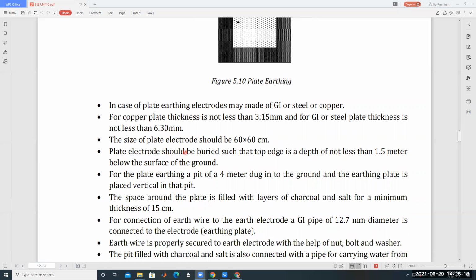The size of the plate electrode should be 60 by 60. Generally we have to maintain this, otherwise 50 by 50. So in general form, 50 by 50 or 60 by 60 centimeters. A plate electrode should be buried such that the top edge is at a depth not less than 1.5 meters below the surface of the ground.